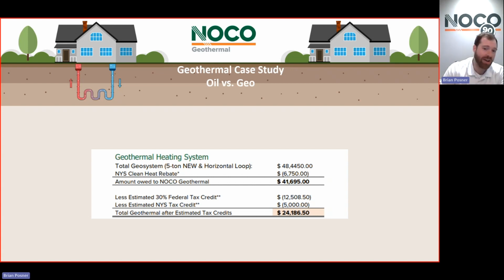Geo is certainly a good 10 grand more expensive than your traditional furnace or boiler. However, if it's going to save you, say, 2 grand on your heating costs next year, taking you from a $2,500 spend to a $500 spend, and it's going to do your AC with that and save you another grand in AC, well, if you're saving a couple grand a year, paying an extra 10 grand for your heating system is a good move because you're going to make that money back in 5 years. And then for the next 25 plus years the system's alive, you're going to be spending a lot less than your neighbors and a lot less than you would have otherwise.